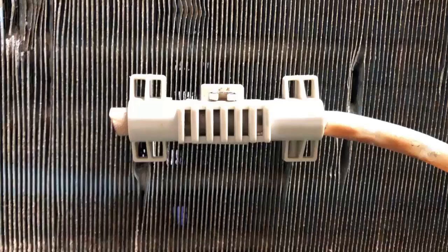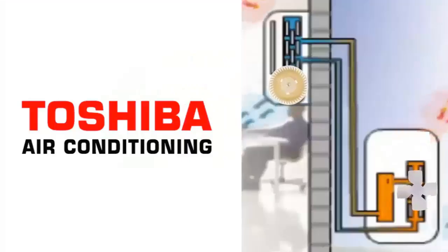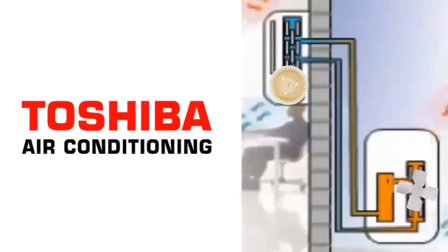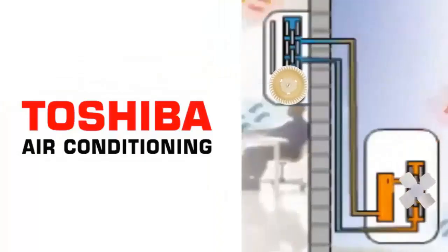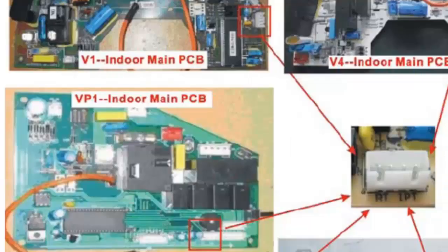3. Check the sensor's position. Make sure the sensor is properly placed and securely positioned. 4. Ensure that the sensor's connections to the electronic board are secure and that the wires are not damaged. 5. Disconnect and reconnect the sensor. Clean the connections if necessary.